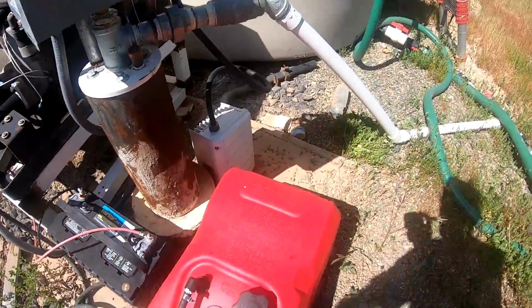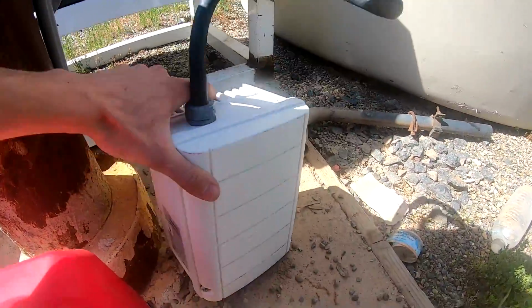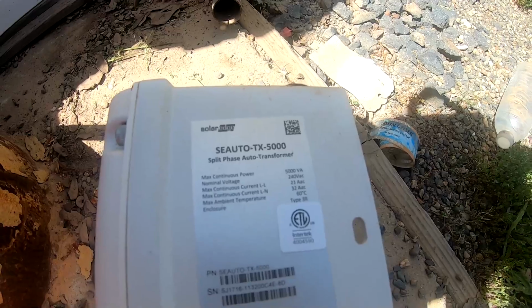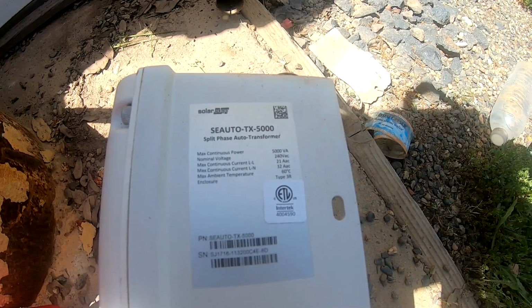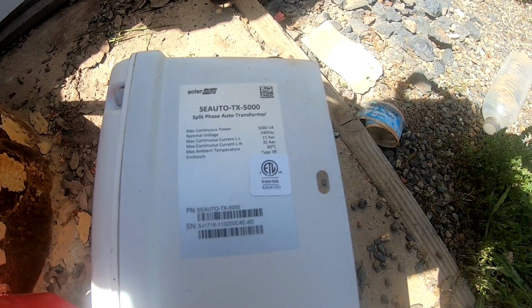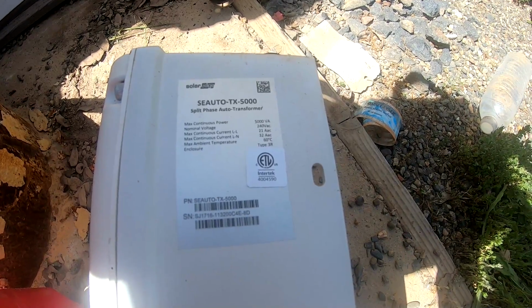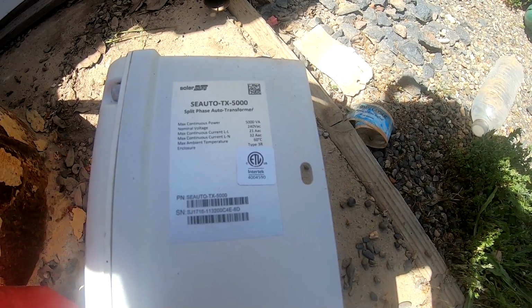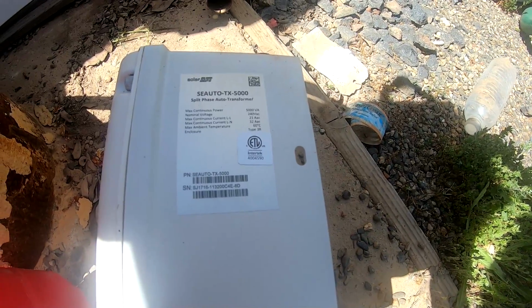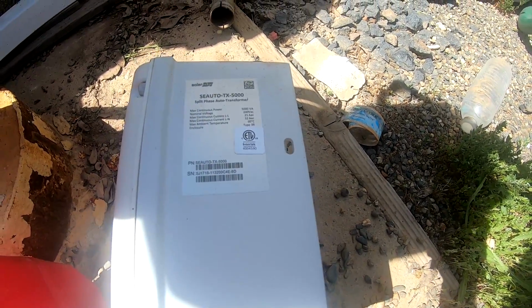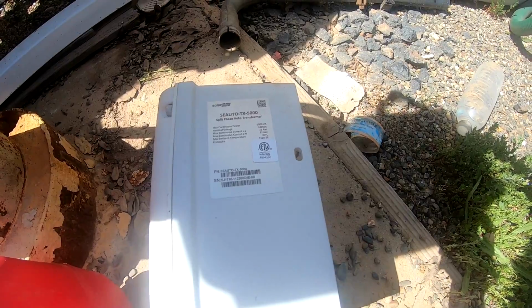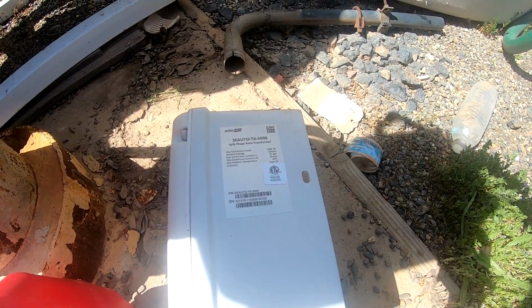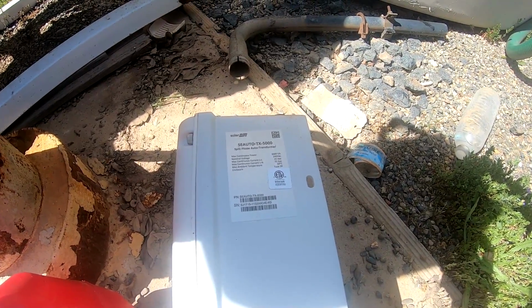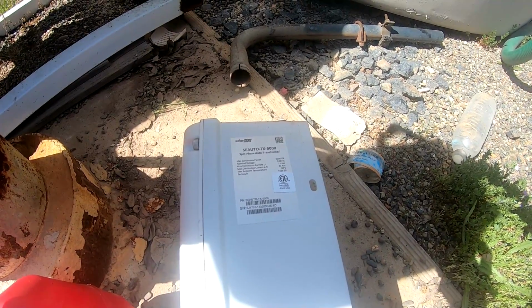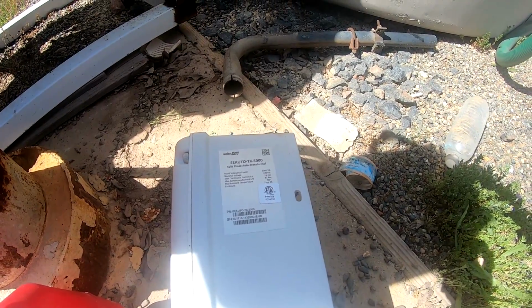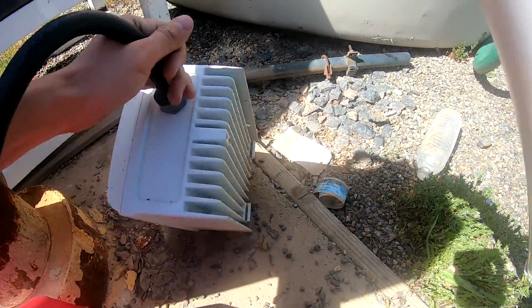I have an auto transformer around the back, and on its label it says Solar Edge TX 5000 split phase auto transformer. It's 5 kVA, 240 volts AC, and in this application it turns 120 volts into 240 volts. Even though it's only 5 kVA, that means it's only producing or transforming 5 kVA on the second leg, so you really get 10 kVA at 240 volts because it's only dealing with half the power.